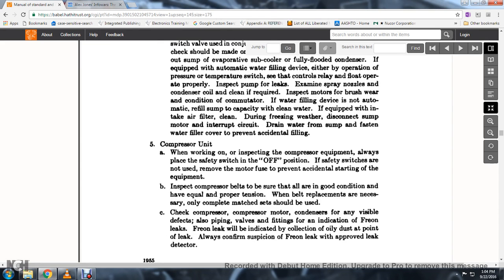12. Inspect the compressor belts to be sure that all belts have equal and proper tension. When belt replacement is necessary, only a complete matched set should be used. 13. Check the compressor and compressor motors to ensure no visible defects, also check pipes and valves.